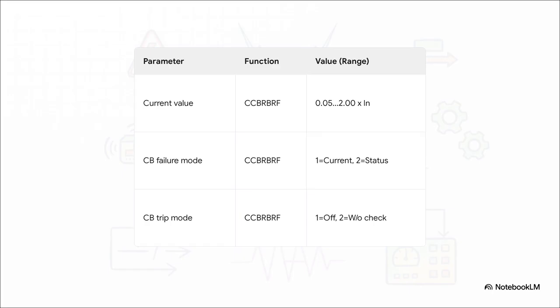To put this into perspective, let's look at some real-world commissioning parameters from an ABB RET615 relay. Engineers have to explicitly configure these current thresholds to detect a failure. They even choose the failure mode, meaning whether the relay relies purely on measuring current, checking the breaker's auxiliary status contacts, or a combo of both. It really grounds all this theory into hard commissioning reality.